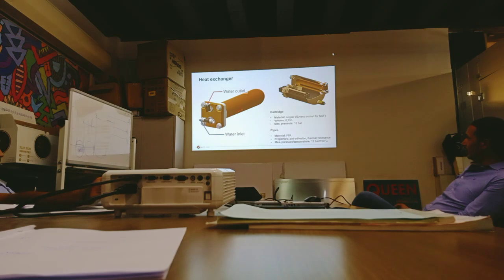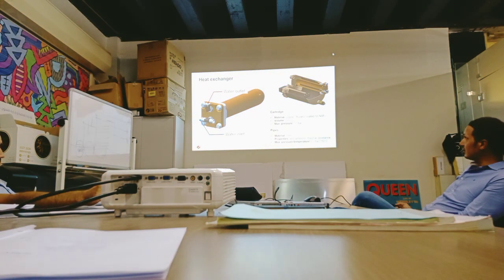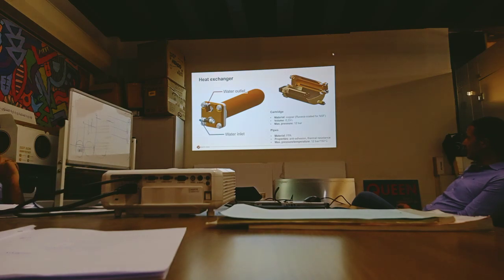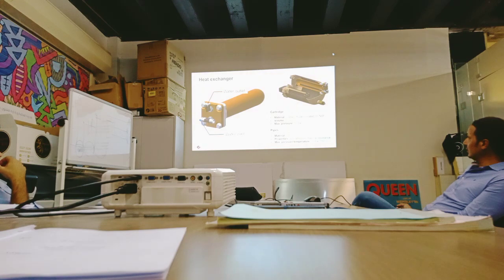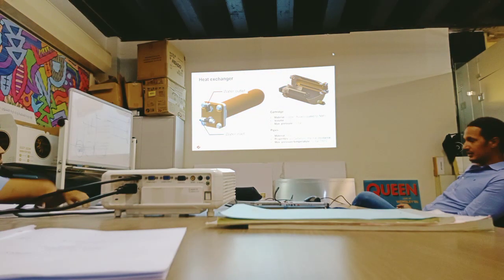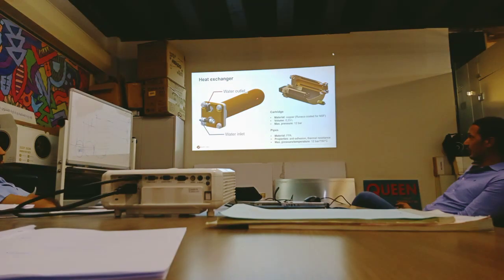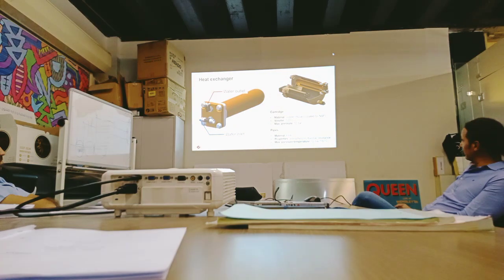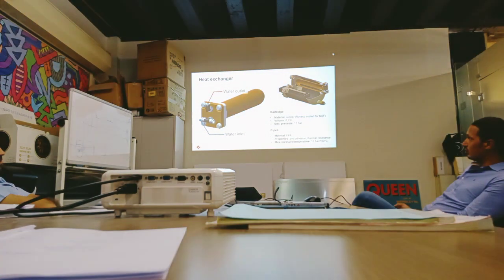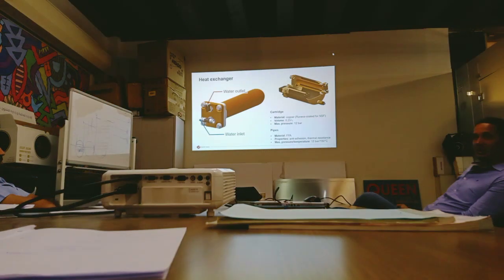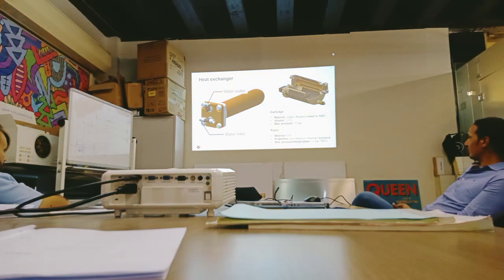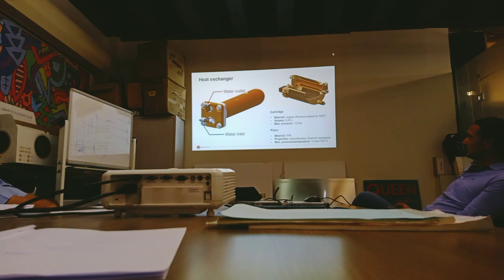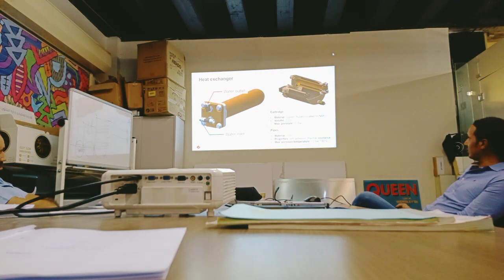The capacity, the volume of this heat exchanger, which is always 100% full with water, there is no steam. It's 0.23 liter, and the pressure can resist to maximum 12 bar. That's why we put this expansion valve as a safety mechanical device to protect the circuit from this pressure, which the heat exchanger itself cannot resist to more than that. The pipe, as you can see here, we don't use copper. We are using this type of pipe, which we call FPE. It's a material which is resistant to temperature and to pressure, which is also easy to connect and disconnect with these fast connectors.